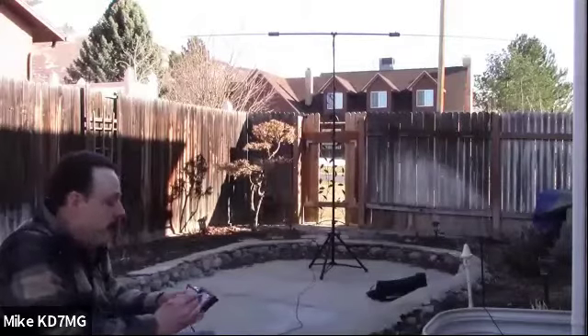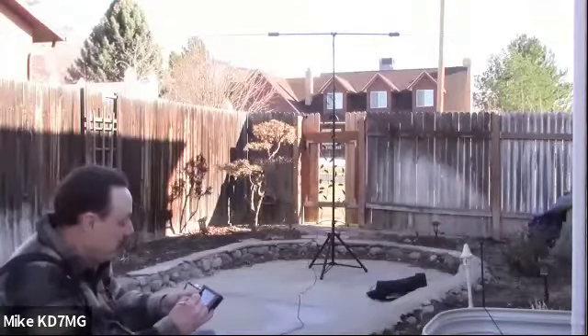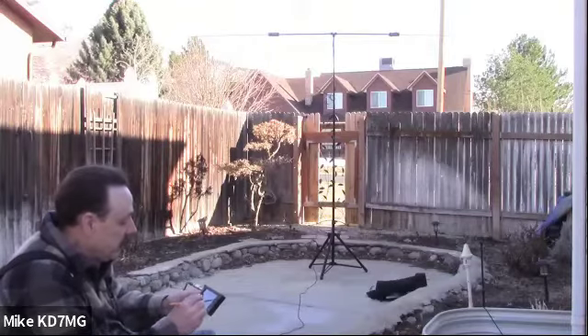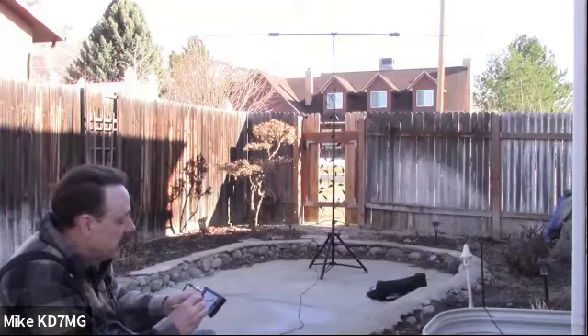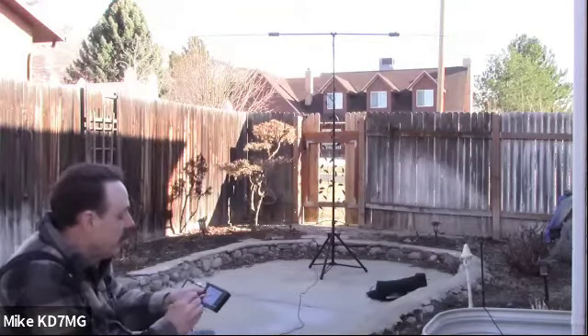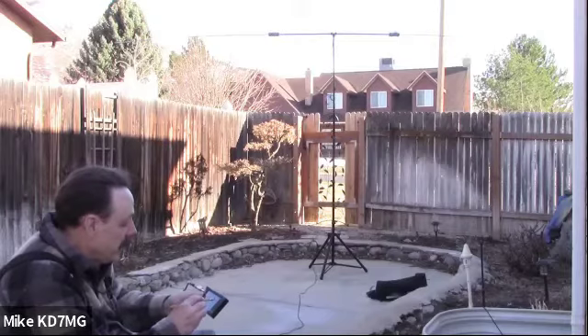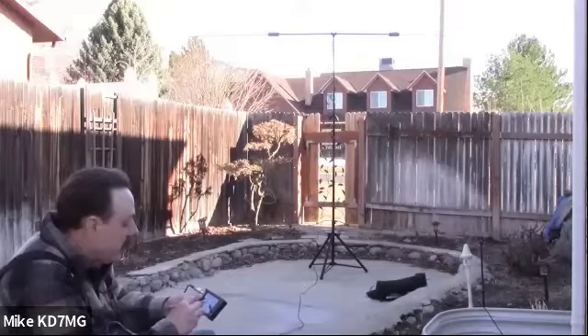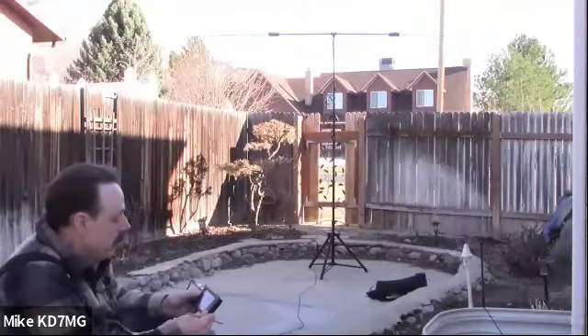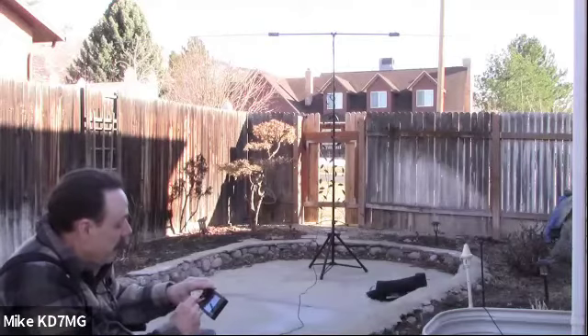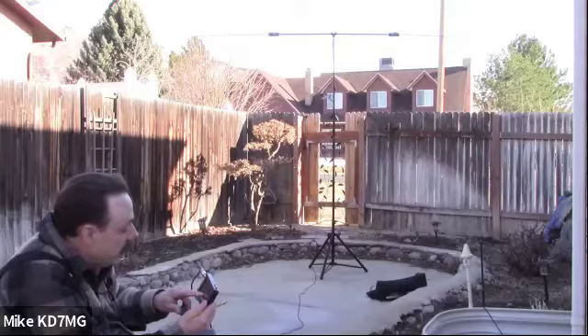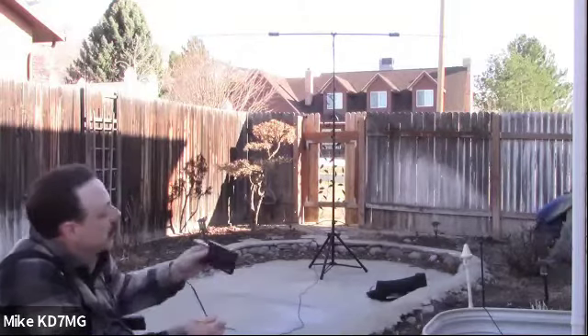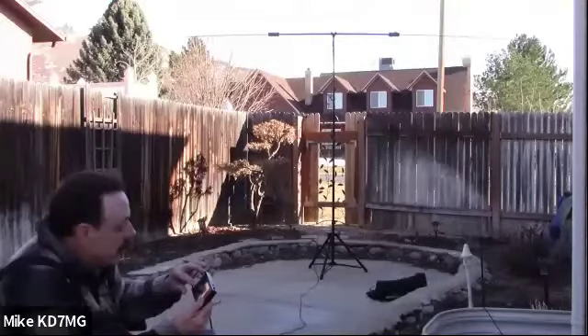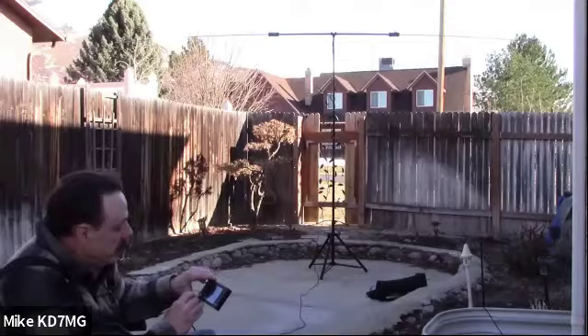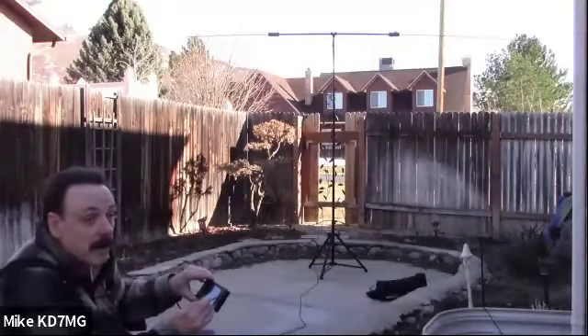alrighty, let's set. I know you can't see this, but we'll go through the process. Start frequency of 20-meter band, 14 megahertz, and a stop frequency of 14.35 megahertz. All right, there's the 20-meter band. It's not bad, but not great. It is about 3-to-1 mid-band, 2-to-1, and up to about a 4-to-1 at the end, high end of the band.